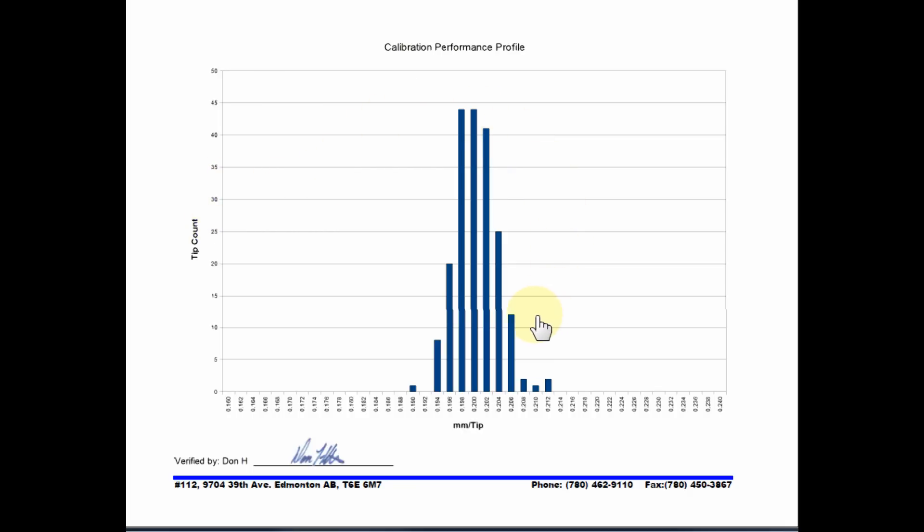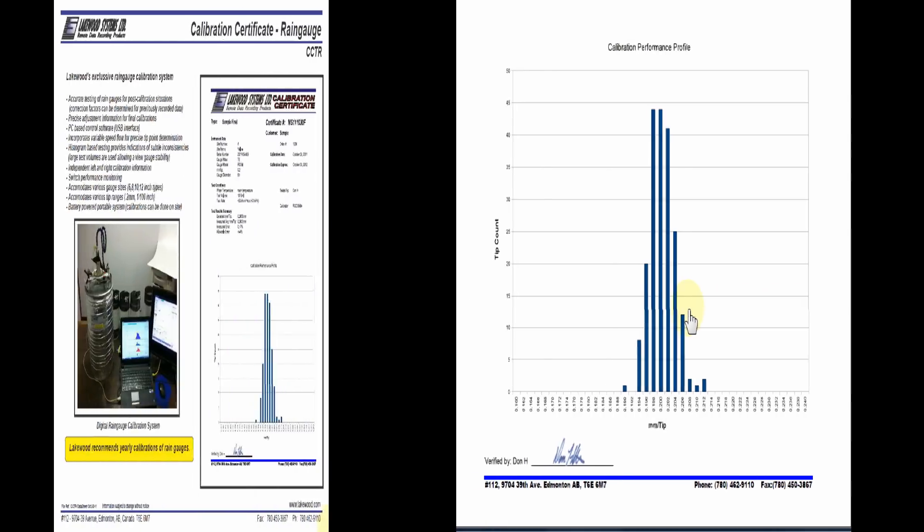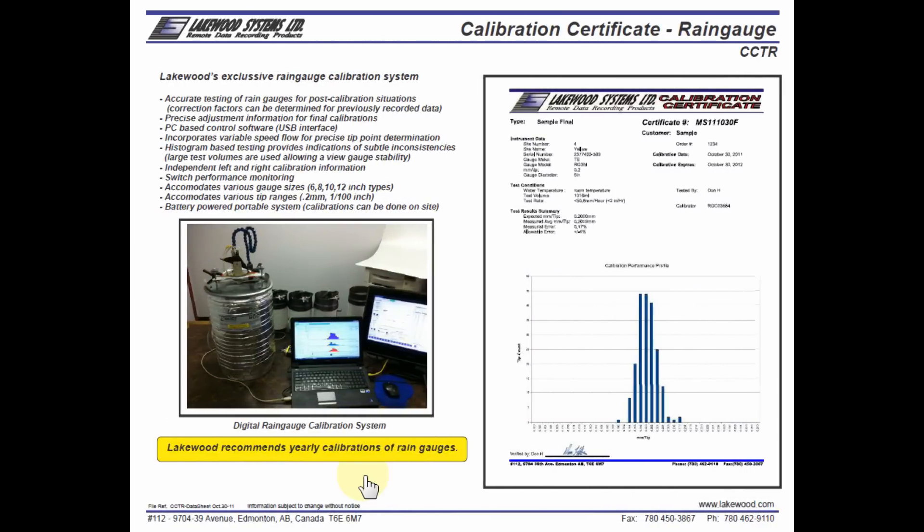And that's the overview of the rain gauge calibration system. It's generally recommended that tipping bucket type rain gauges be calibrated at least once a year. If you'd like your rain gauges calibrated, please contact Lakewood Systems at 780-462-9110.